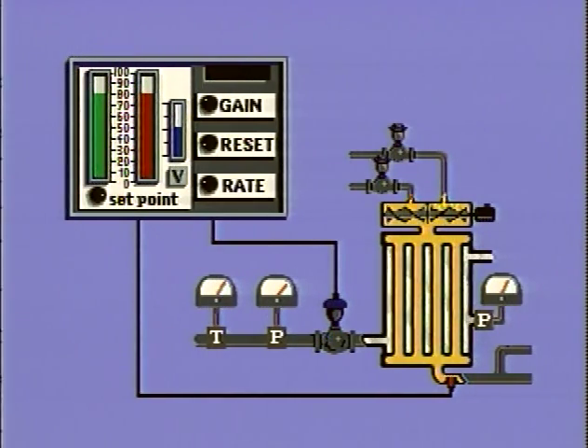Here is why. Maintaining the product at set point required that steam be supplied to the heat exchanger at a constant rate. If the pressure of the steam supply fell, then the quantity of steam had to be increased to compensate. The pressure of the steam in the heat exchanger would change rapidly if there was any pressure change in the steam line. The steam pressure in the shell was the variable they chose to monitor in a control system that would respond quickly to changes in the steam supply.